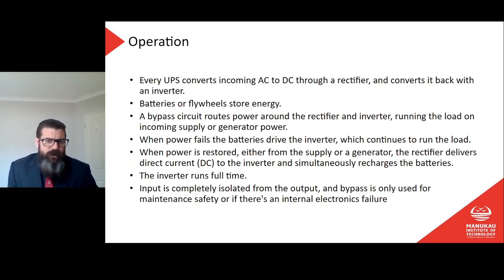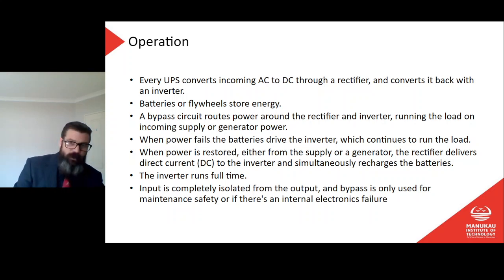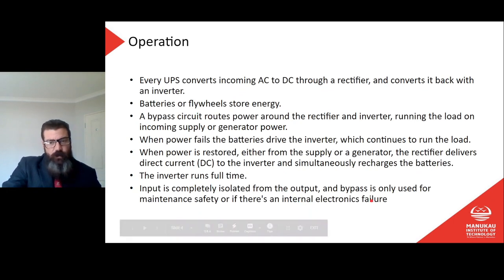A bypass circuit routes power around the rectifier and inverter, running the load on the incoming supply or generator power, so that's our normal power. When power fails, the batteries drive the inverter, which continues to run the load. When power is restored, either from the supply or a generator, the rectifier delivers direct current into the inverter and simultaneously recharges the batteries. The inverter runs full time. Input is completely isolated from the output, and bypass is only used for maintenance, safety, or if there's an internal electronics failure. Okay, there we go.